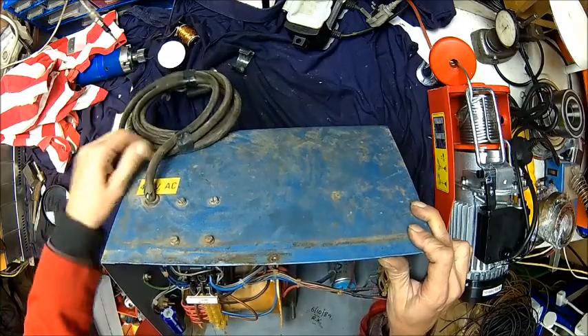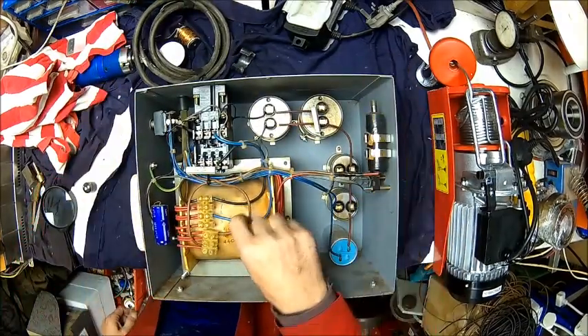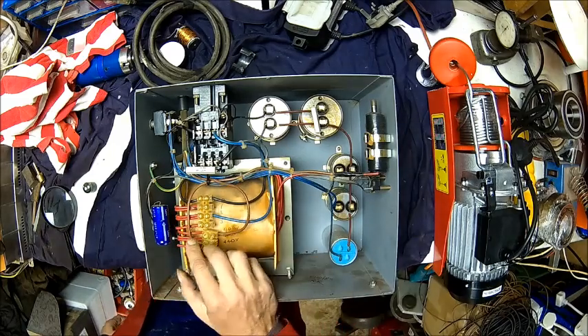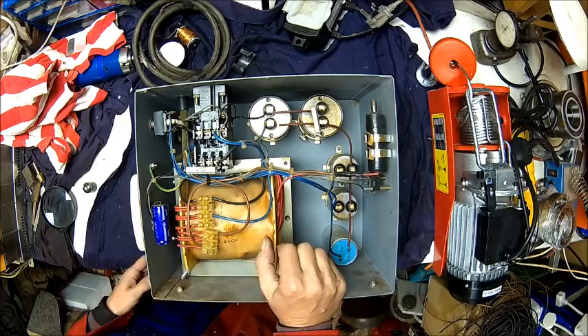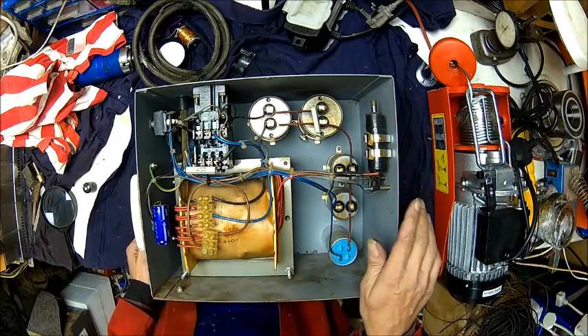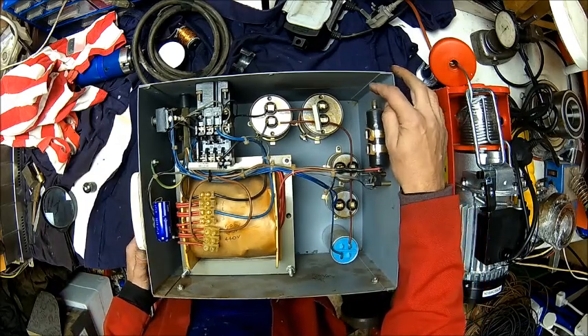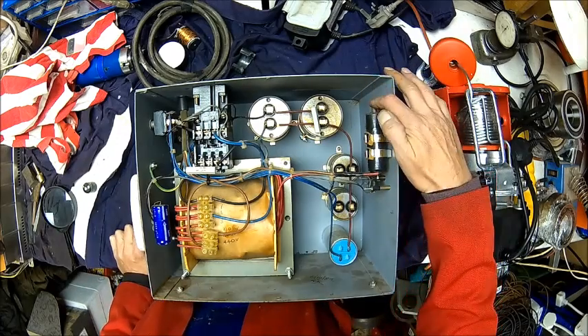The cable is broken here. It's already set to 400V. Let's change that capacitor and put a cable on, put a plug on. This is an old style one - no electronics. This is a current sensing coil; it just flicks a switch here.